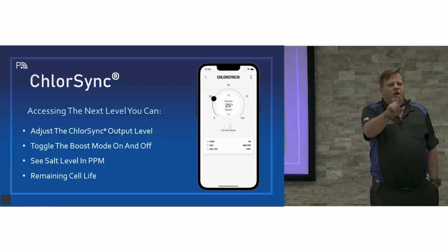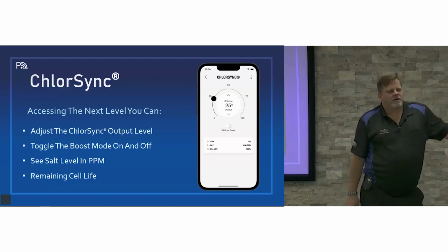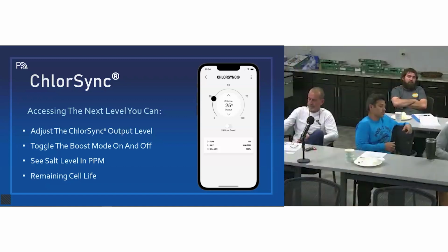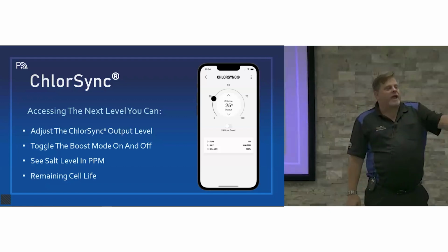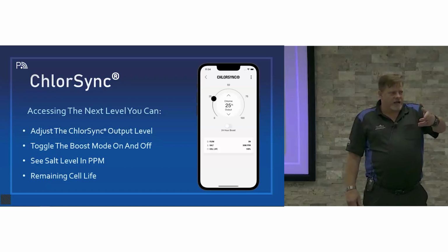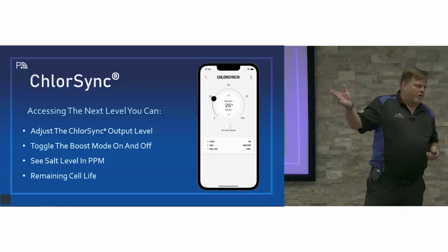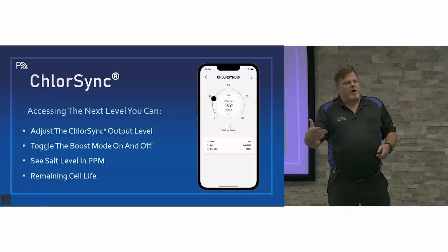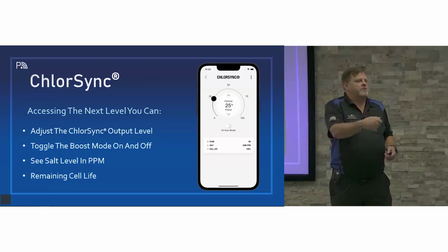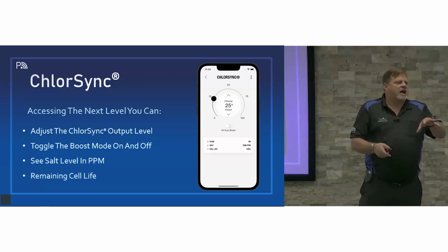But if they had a—hold on, talking about the spa pool combos—you can also set it up so that when you're in spa mode, you activate the dry contact and plug into the automatic cover. There is a fix for that. There's no dedicated spa mode setting, so you can't set a percentage specifically for spa mode, but you can activate the pool cover switch when it's in spa mode, which will allow the system to drop the percentage. So there is kind of a workaround for that.